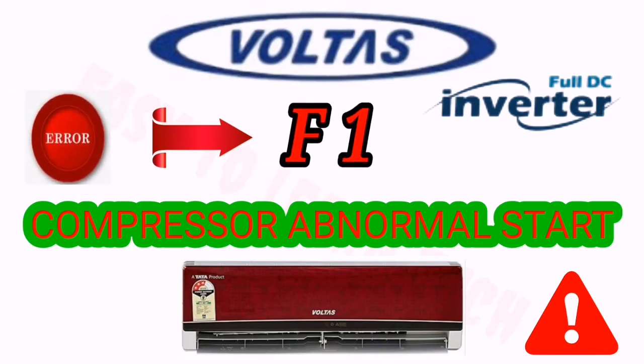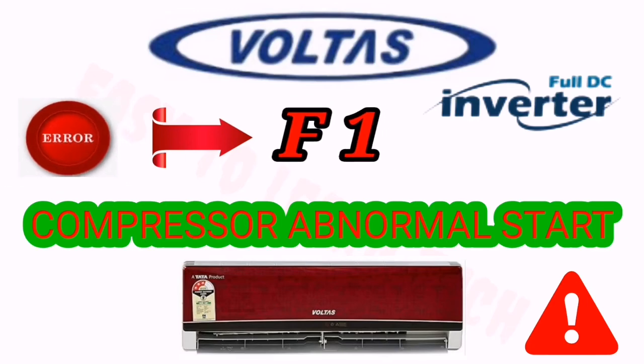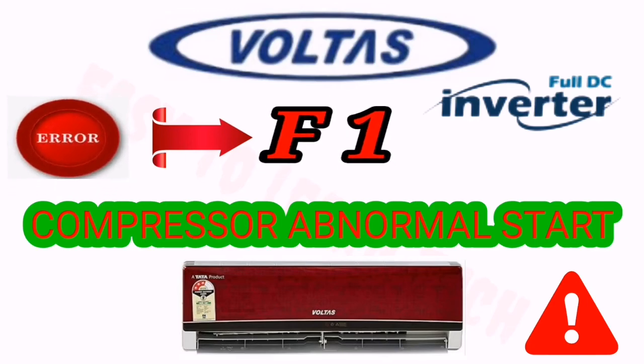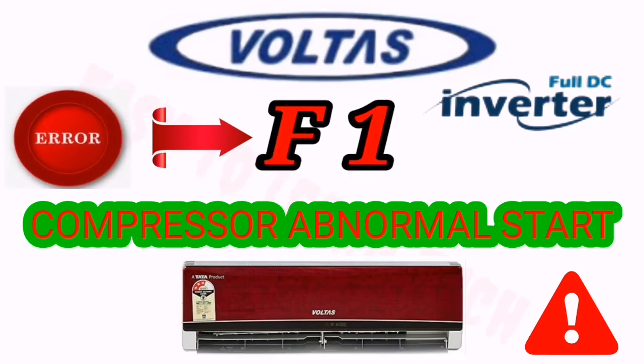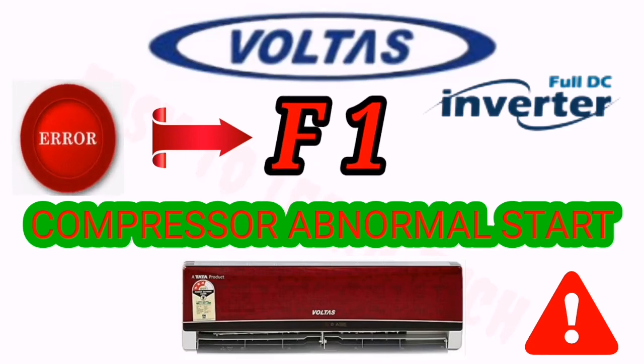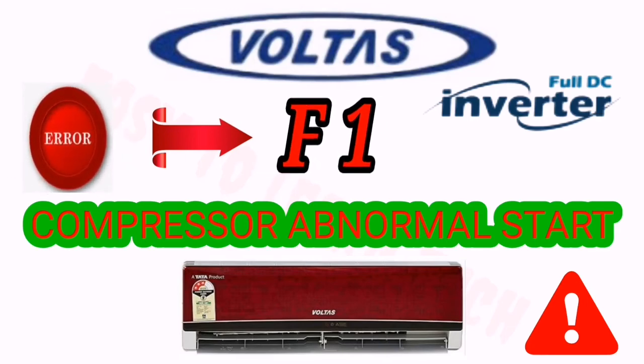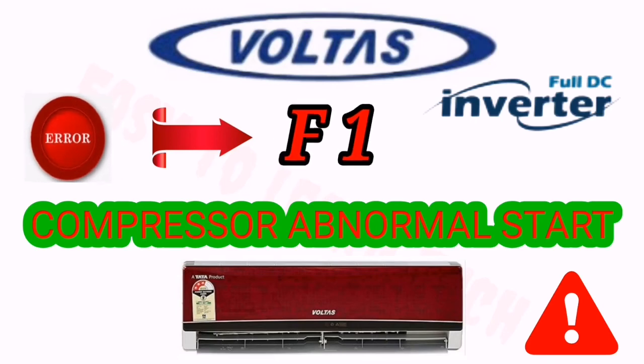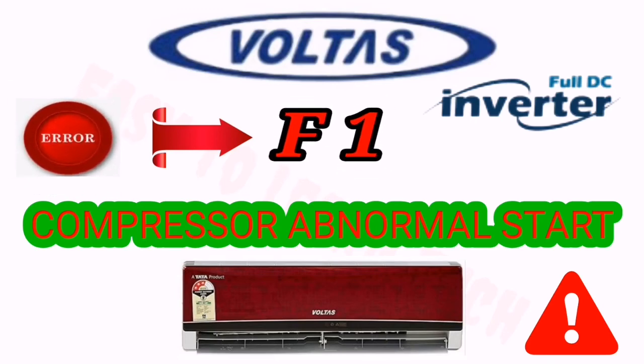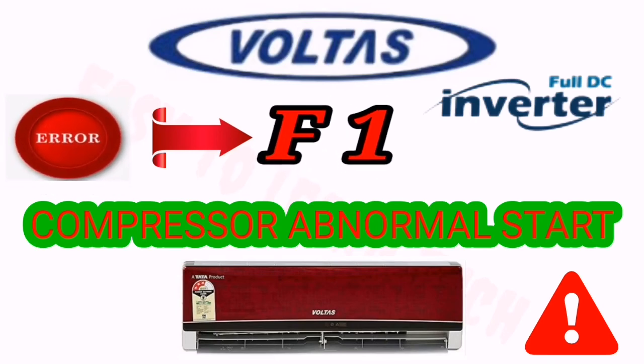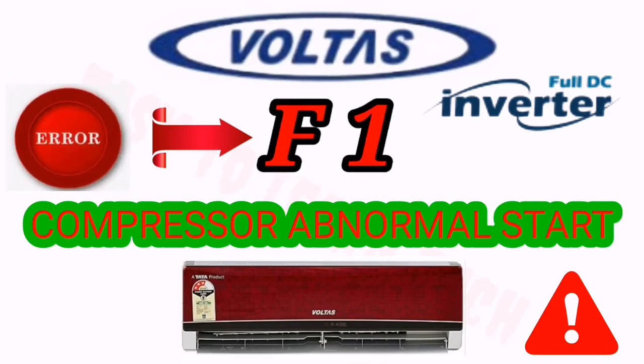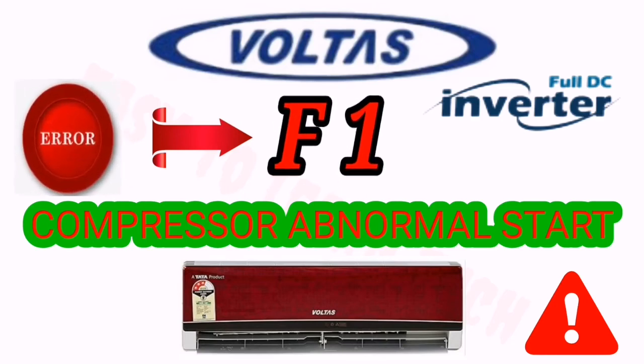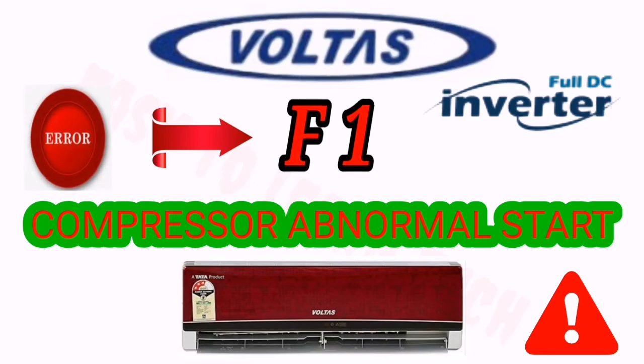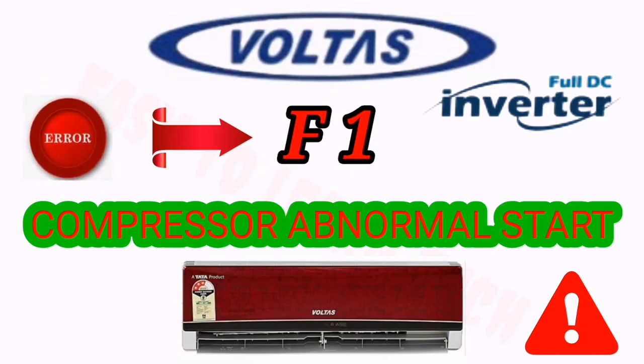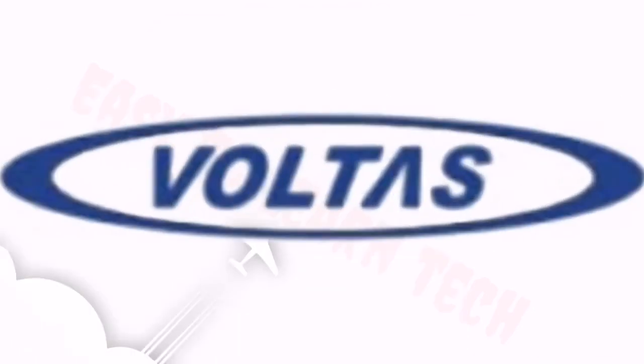Then you have to check our outdoor PCB. In the outdoor PCB, you have to check the cable going to our compressor, UVW, whether it is properly connected or not. If it is not properly connected, connect it properly and start the unit. And again, if you are getting the same error, then you have to check the output supply which is coming from our outdoor PCB to our compressor. You have to check whether the power supply coming from UVW is okay or not. If it is not okay, then you have to change the outdoor PCB. Our unit will be in working condition.